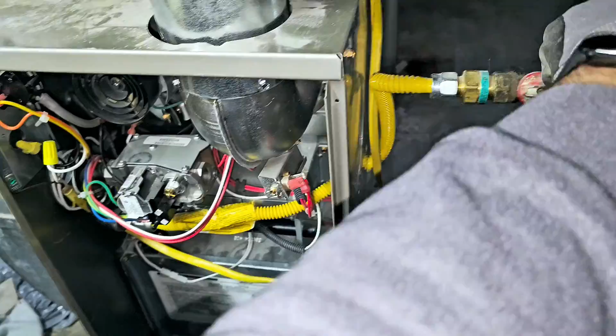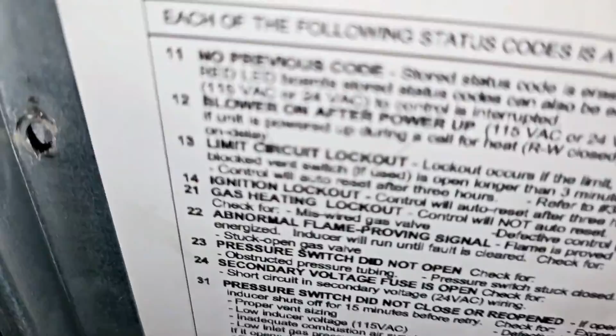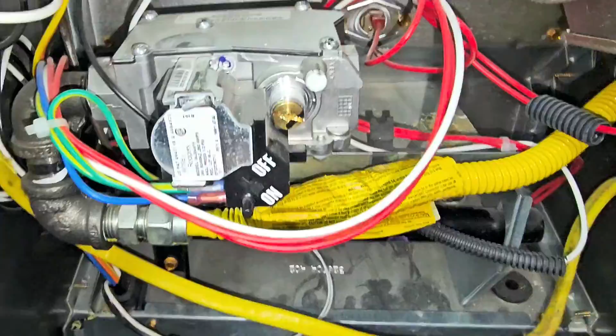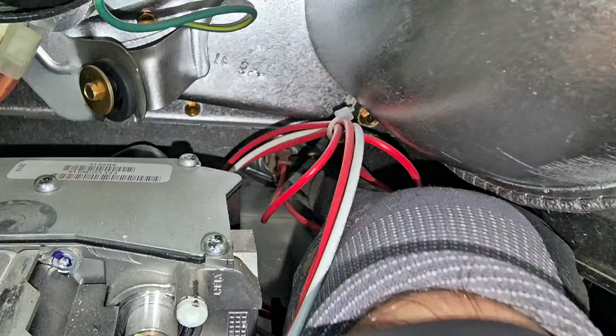Now, this is a Bryant furnace, and I had a code, and it was 13, limit circuit lockout. So that means the limit switch is opening. That's the limit switch. Why was it opening? Because it was overheating, getting too hot. And that's why, not enough airflow. So we're going to take this coil out today. We're going to take it outside and we're going to clean it. Then we're going to put it back in.